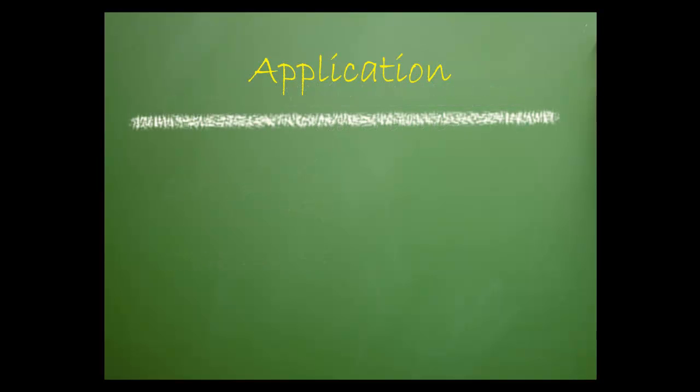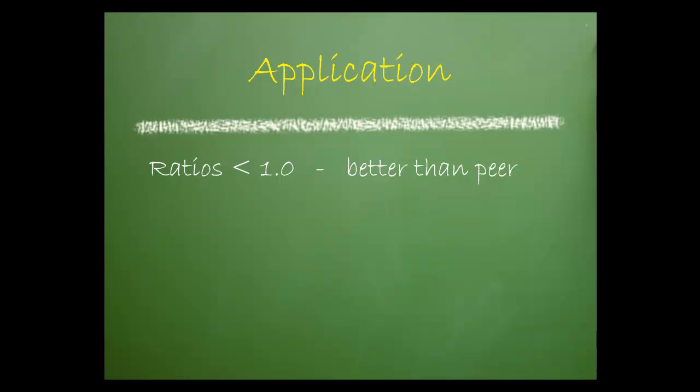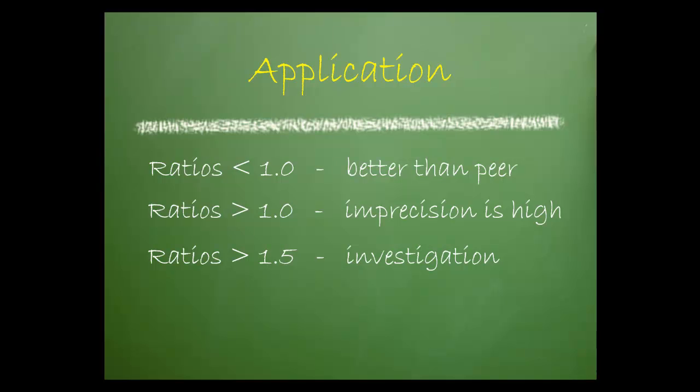What does all this mean? Well, any ratio that's less than 1 indicates that precision is better than the peer group. A score greater than 1 indicates that imprecision is larger. Ratios greater than 1.5 indicate a need to investigate the cause of the imprecision. And any ratio greater than 2 usually indicates a need for troubleshooting and or corrective action. Something in the test system is causing an increased imprecision and the patient results may not be entirely reliable.